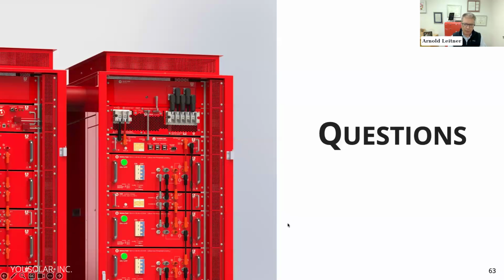A very important question, something we've addressed head on, no pun intended, since we have a hood on this cabinet, is temperature. There's a limit to how high lithium iron phosphate batteries can operate, and this has nothing to do with the brand, it's purely the physics of the chemistry, about 116 degrees Fahrenheit. Therefore we require that all PowerBlocs are in a temperature-controlled environment, meaning air conditioning. But we will waive that requirement for climate zones where we're comfortable that just venting the system, either passive or active with the vent hood you see on top, which can connect to a plenum and an active heat venting system, is sufficient. We can waive and approve that on a location-by-location basis, but that's true for all systems. The PowerBloc does have internal heating for the batteries, so we're not too worried about being somewhere that gets a little cool, the battery packs will be heated. We don't want to heat the power electronics though, because the colder it is, the better it operates.